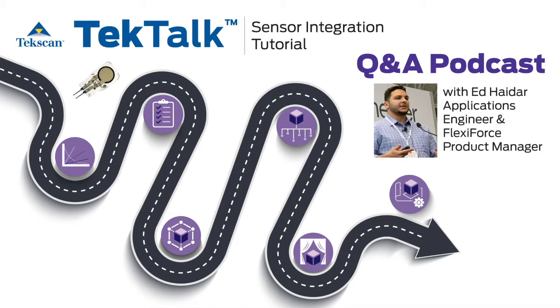Now let's say for your given application, you need to power the sensor with a higher voltage, and a reason for that might be, for example, you need more sensitivity out of the sensor or more measurement resolution. If you want to go higher, to 2, 3, even 5 volts, the recommendation is to use a square wave there so that the sensor has more off time during the measurement. This will help preserve the sensor life and still get the maximum possible sensor life out of the product.